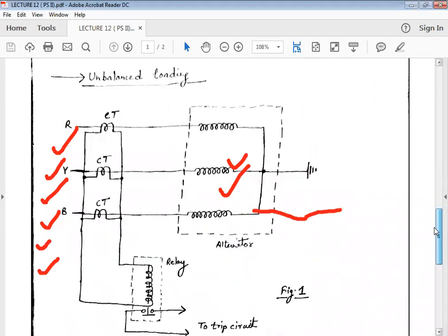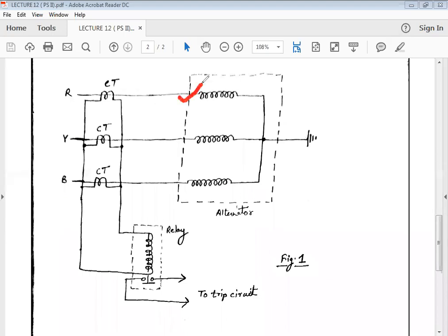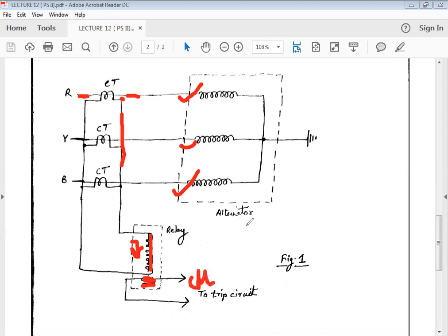There is a diagram showing how protection can be provided against the fault. Here are the three phases of the alternator. Current transformers are connected across all three phases. Whenever there is normal current flowing with no fault condition, the current at both ends is equal, so there is no net current flowing through the relay operating coil and the trip circuit remains open. Whenever there is a sudden fault, the current values at both ends change and the difference in current starts flowing through the relay operating coil. When current flows through the relay operating coil, the trip circuit closes its contacts, which in turn opens the contacts of the circuit breaker and removes the alternator from the faulty section.